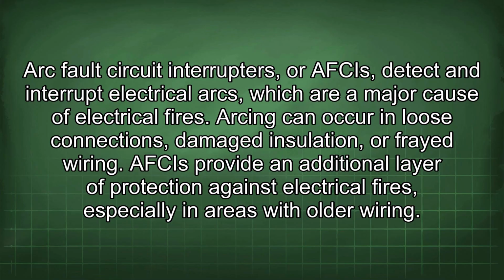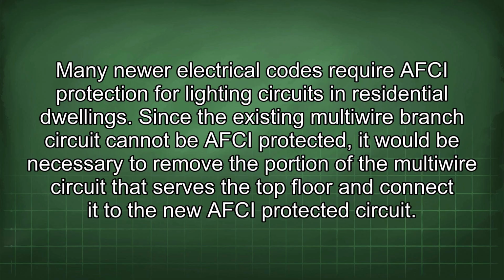Arc fault circuit interrupters, or AFCIs, detect and interrupt electrical arcs, which are a major cause of electrical fires. Arcing can occur in loose connections, damaged insulation, or frayed wiring. AFCIs provide an additional layer of protection against electrical fires, especially in areas with older wiring. Many newer electrical codes require AFCI protection for lighting circuits in residential dwellings.